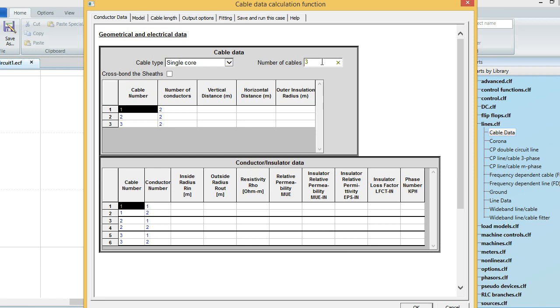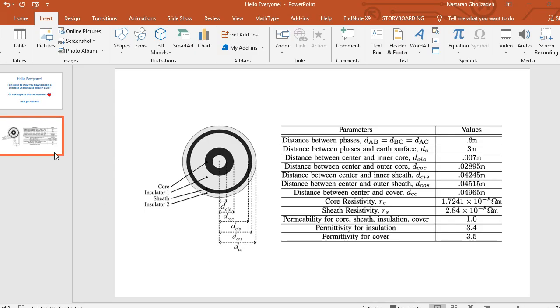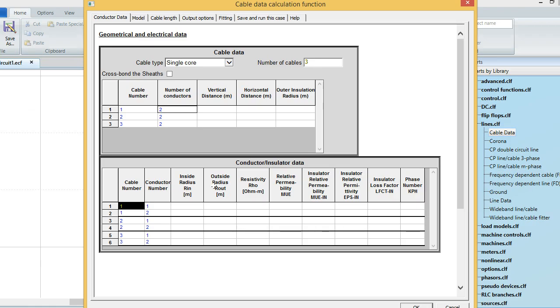I have three phases and each phase has two conductors. Because here you can see that we have one core, an insulator around that, a sheath, and an insulator around that one as well. So core and sheath are both conductors — that gives two conductors per cable. So number of conductors is two.